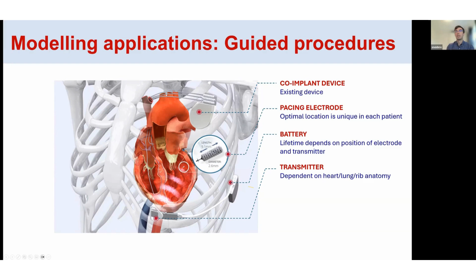And the problem they had was that they wanted to implant everything all at once, and that meant that you needed to ensure that the ultrasound transducer was able to deliver energy to where you were going to plant the electrode. But the way they were doing it was implanting the transducer and then working out where they could put the electrode afterwards. And this led to some mismatches between energy delivery and energy requirements, which was causing problems for the patients. So what they wanted was a pre-planning system where they could put all of this information together for a patient and plan where they were going to put everything before they did the original procedure.